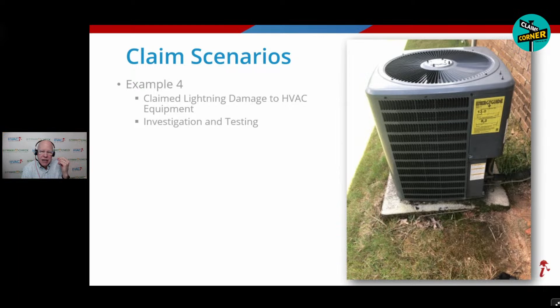What's the next step? Next step is the acid test. I described it to you before, and I'm going to show you. You pull out the new acid test, it's yellow, like this. The technician opens up the little service valve, plugs it on there, runs just a little bit of refrigerant over it. If it changes color at all - could be off yellow, a little orange, orange-brown, red, even pink and purple, those are really bad - it doesn't matter which color it changes to.